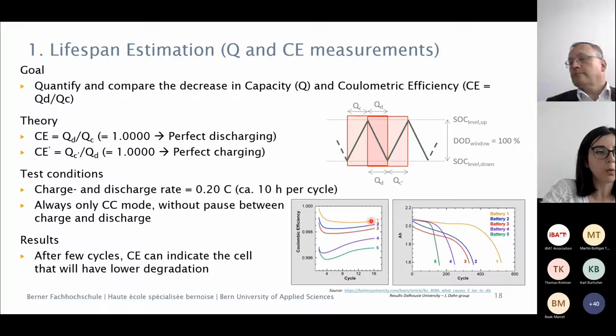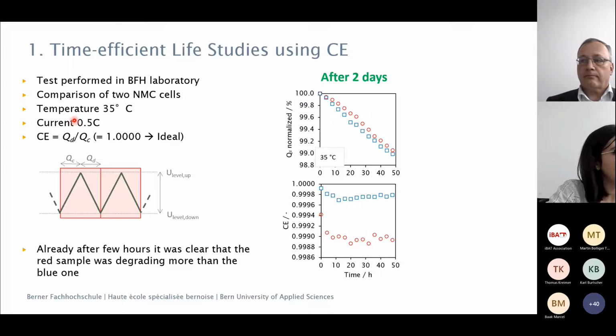So generally what you would like to have is to perform those measurements. You need to have a high precision tester that can quantify this variable, and you want to have the value of this capacity ratio closer to 1. And actually, this is one of the tests that we perform in our laboratory, and here we just reported the normalized capacity fading after 2 days of 2 batteries, the red and the blue. And at the beginning, it seems that, for example, the red battery was performing a bit better than the blue, but looking at the Coulombic efficiency measurement, actually the blue battery was closer to 1 than the red one.